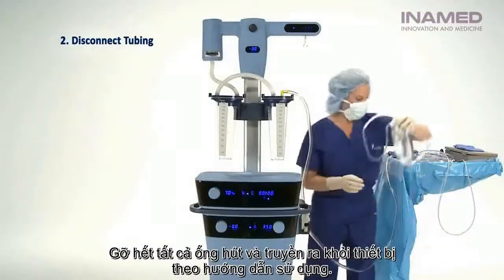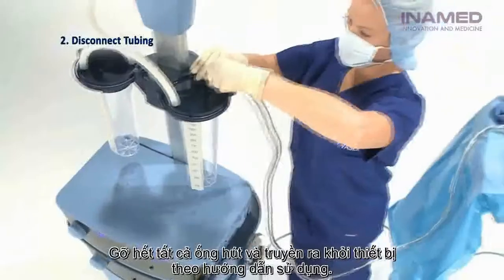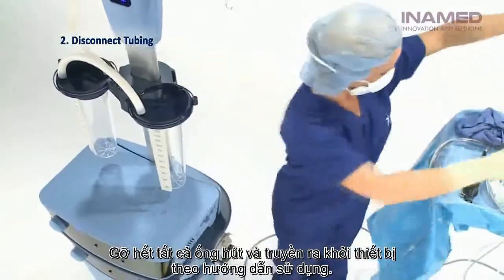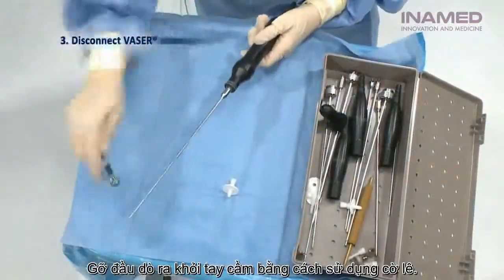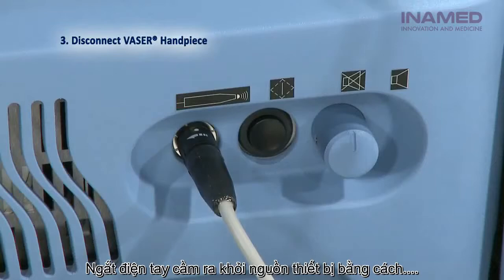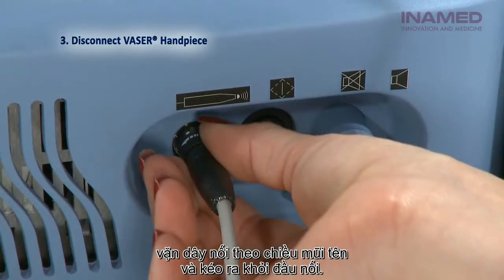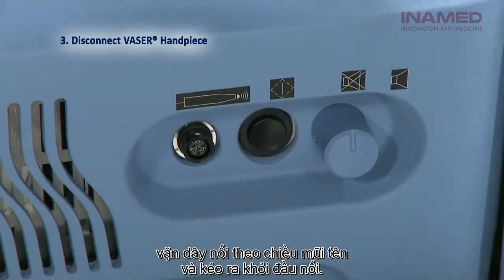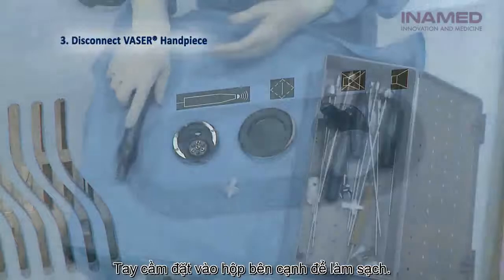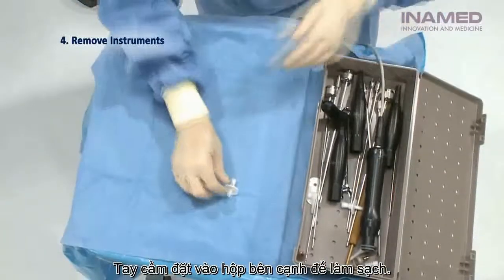Disconnect the suction and infiltration tubing. Dispose of the tubing in accordance with your institution's guidelines. Remove the Vaser probe from the Vaser handpiece using the Vaser wrench, then disconnect the Vaser handpiece from the amplifier. Twist the outside collar of the handpiece connector as the arrow indicates, and pull away from the amplifier receptacle to release it. Set the handpiece aside for cleaning.